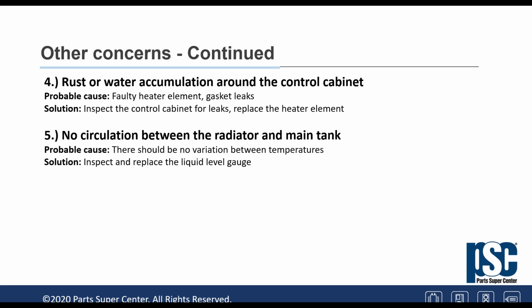This is very important: no circulation between the radiators and the main tank. Again, there should be no variation in temperature in between, correct? The level of the oil at 25 degrees C should be halfway up the opening of the top radiator's manifold. In other words, if the manifold of the radiator on the top and bottom is about 5 to 6 inches, the oil level at 25 degrees C should be at least halfway, 3 inches.